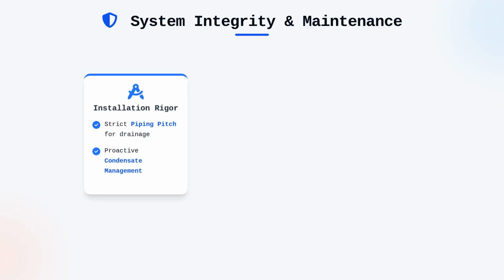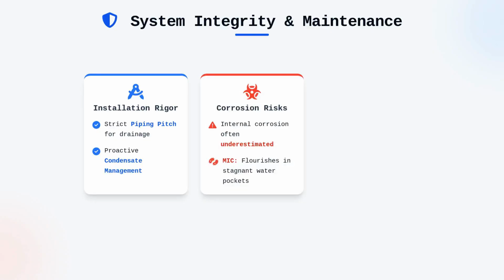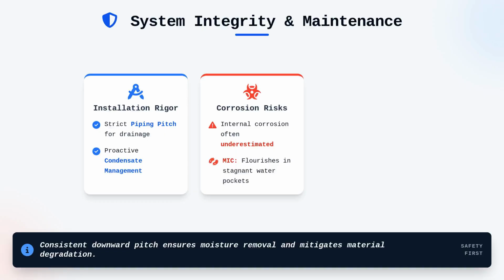Maintaining the integrity of these systems involves rigorous attention to installation details, such as piping pitch and condensate management. Because dry air contains minimal moisture, the potential for internal corrosion is often underestimated until it results in blockages. Microbiologically influenced corrosion, commonly known as MIC, flourishes in the presence of stagnant water or localized condensation that accumulates in low-point pockets. Requiring a consistent downward pitch toward drains ensures that any internal moisture is removed during routine maintenance, thereby mitigating the risk of material degradation.